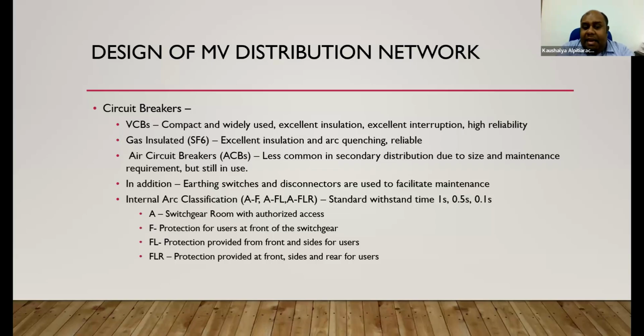use. In addition, there may be earthing switches, disconnectors and some other things to facilitate maintenance. Internal arc classification. This is again another area that we need to focus more on. AF, AFL, AFLR. These are the three classifications, and standard withstand times may be 1 second, 0.5 seconds, and 0.1 seconds. If you don't see any flap or any chamber for arc classification, that means you have a 0.1 second internal arc rated system.